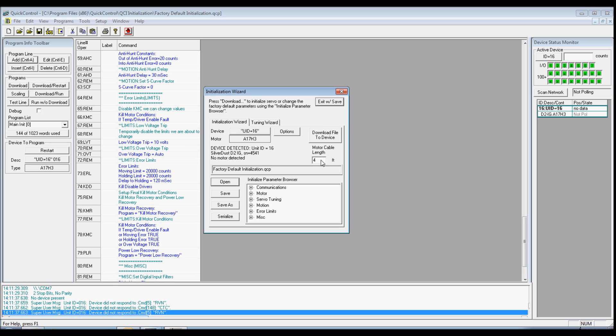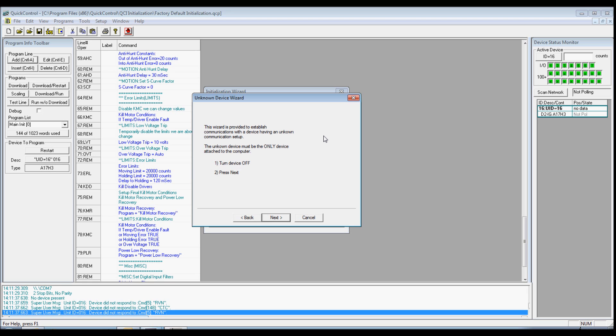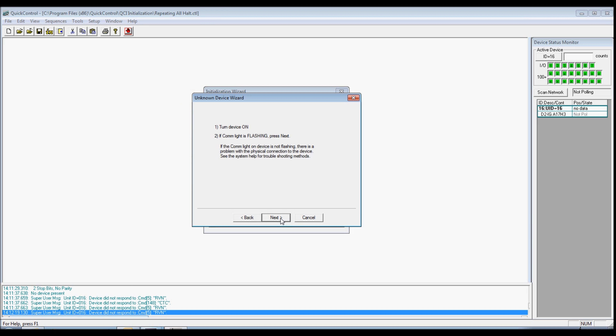Now click Download File to Device to initialize the servo motor using factory defaults. The unknown device wizard will pop up. Power down your controller and click Next. Now power up and verify the red COM light on the controller is flashing. If it is, then click Next.